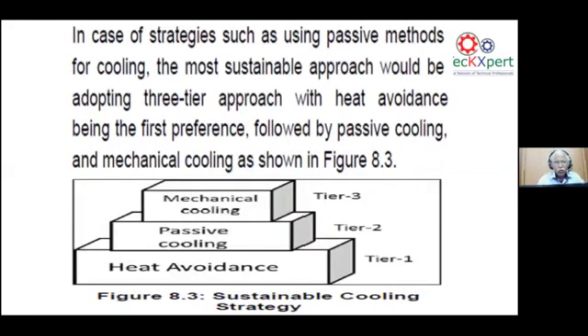So we have to go for a 3-tier approach, especially for air conditioning in your buildings. One is heat avoidance, that is the first tier, like avoidance of solar heat and solar load, heat load. Then passive cooling, like glazed tiles or glazed windows. And then only do we concentrate on the typical air conditioning or chilled water system, where the kilowatt per ton matters to us.